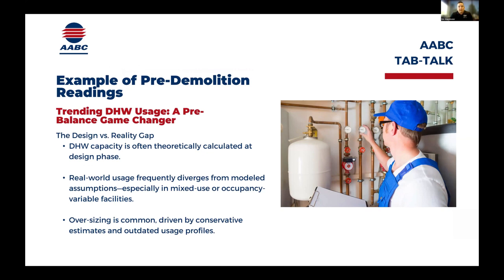We've had some projects in the last five years where they have us trending domestic hot water to resize either the heat exchanger or the boiler for the domestic heating hot water systems. What we've found is a lot of these buildings have been operating for 10 to 20 years, and it was all based on theoretical numbers - we have this many showers, this many sinks, a kitchen, so this is what we think the domestic hot water usage is going to be. But it's all theoretical at that point.